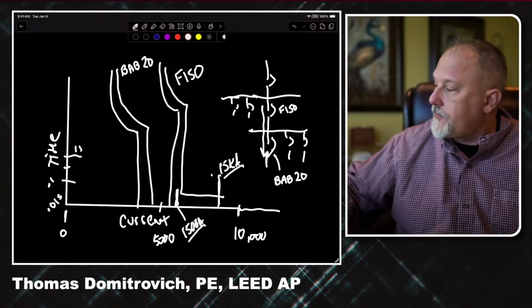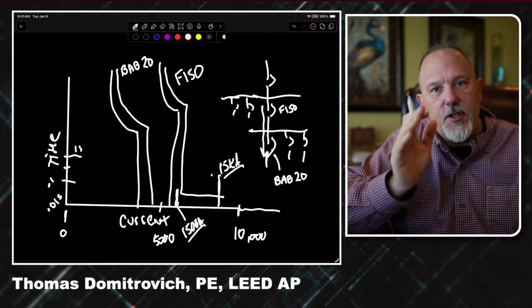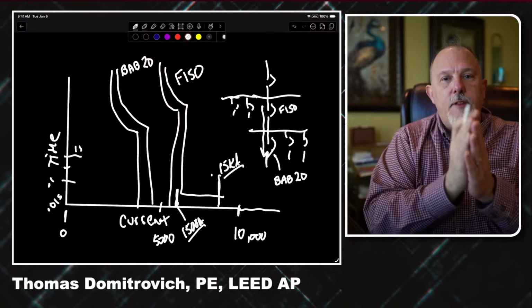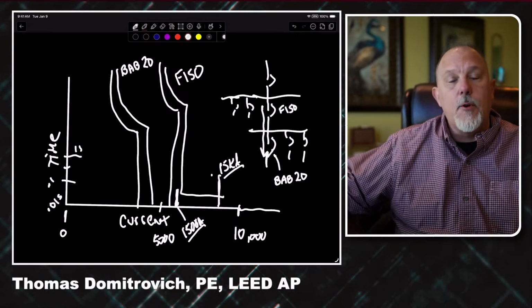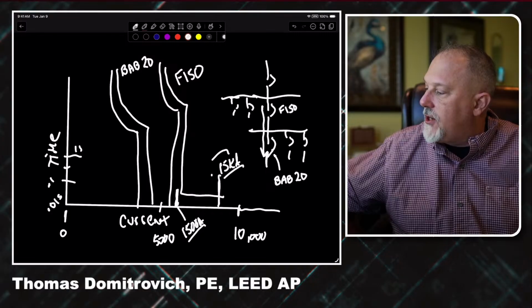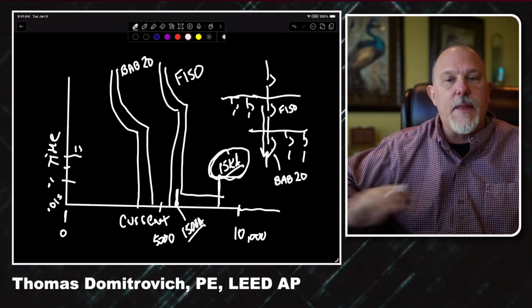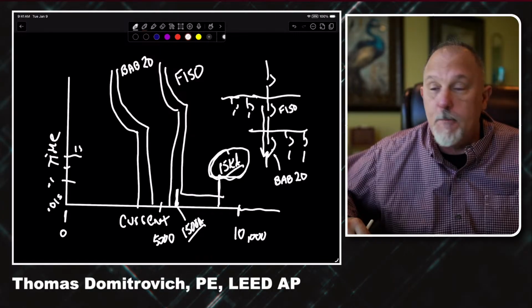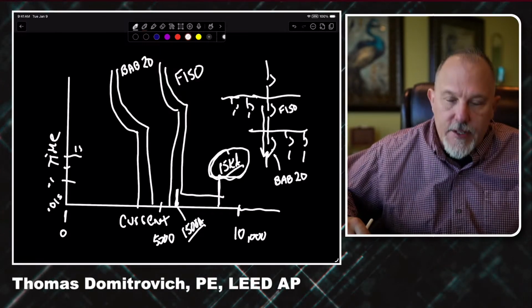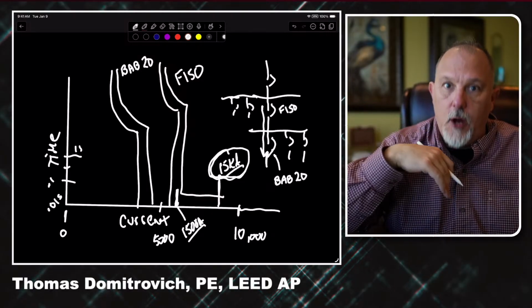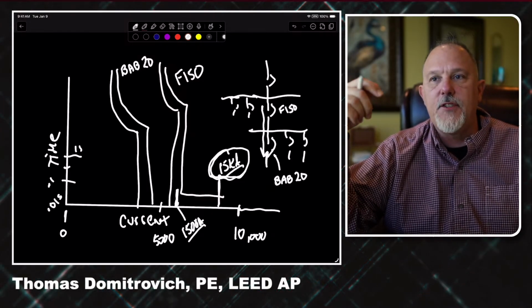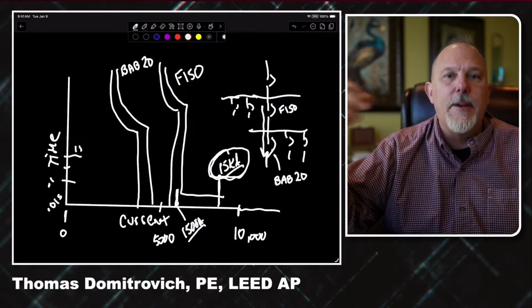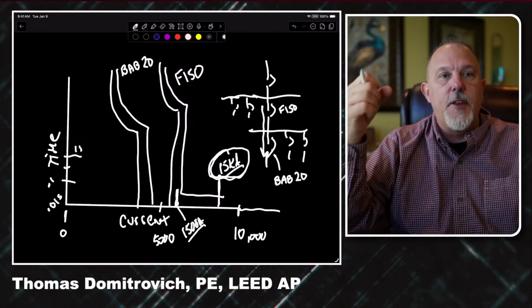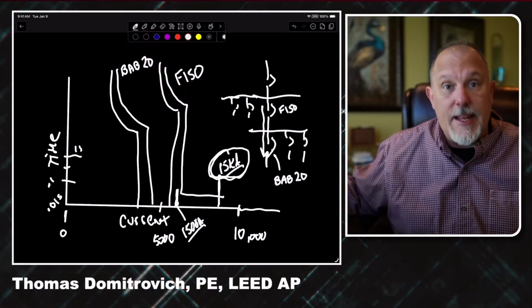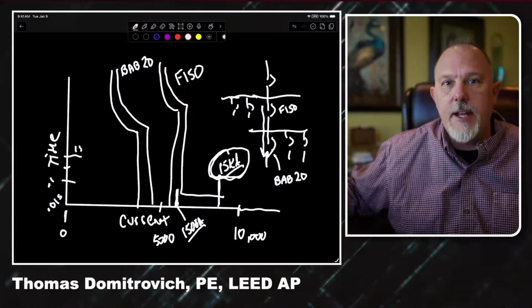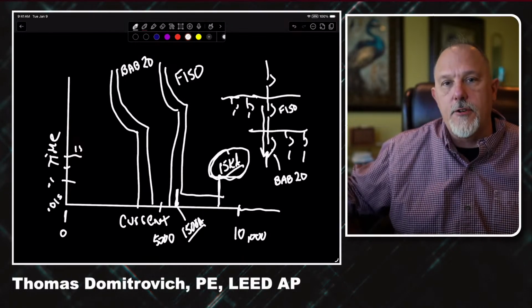All right, so now we know current. We know the fault current. Now, if you and I were going to argue, you may say, Tom, you're never going to see 15,000 amps of fault current value. And I will say, well, I'll never say never, but the chances are pretty low. How might I see it? I would have to bond the bus. I would have to intentionally ground something, because there would have to be zero impedance for you to get that value. So I can understand someone who says that value never occurs.